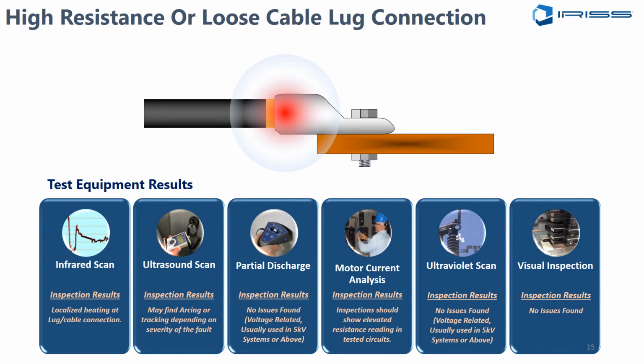You would replace the lug so the whole system is good and rebuild it. Now the reason we do that is if you're shutting down to do this, the last thing you want to do is go back in and change it. Say you need another shutdown because it wasn't the actual connection that was loose, it was the lug. So to save yourself embarrassment, just cut the lug off, replace the whole joint, and then you have a good system there in place.